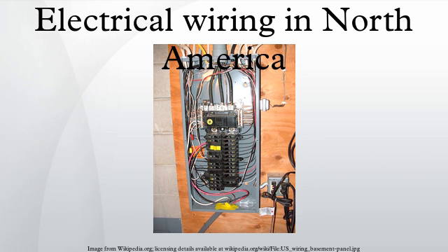Lighting and power receptacle circuits in North American systems are typically radial from a distribution panel containing circuit breakers to protect each branch circuit. The smallest branch circuit rating is 15 amperes, used for general-purpose receptacles and lighting. Often, 20 ampere circuits are used for general-purpose receptacles and lighting. In residential construction, branch circuits for higher ratings are usually dedicated to one appliance, for example, fixed cooking appliances, electric clothes dryers, and air conditioners.